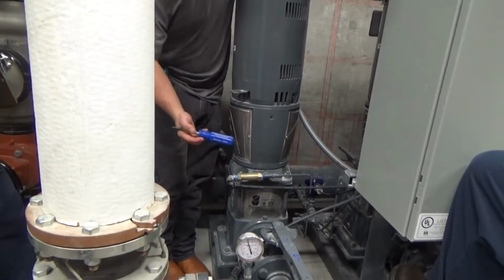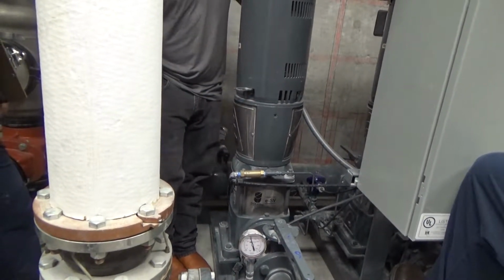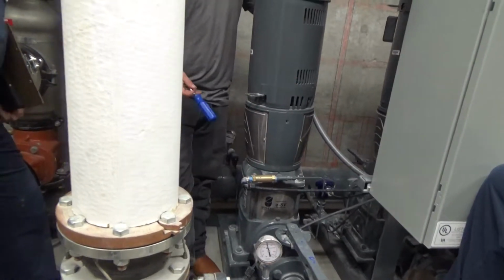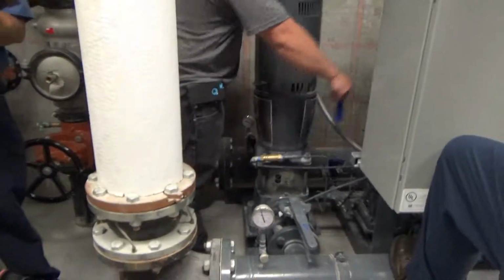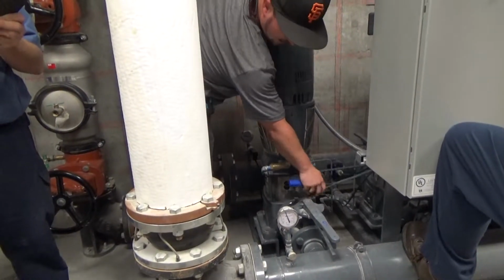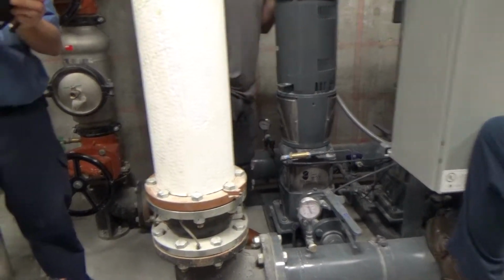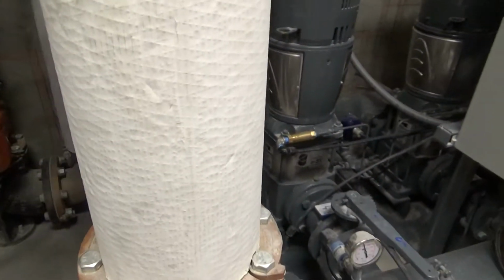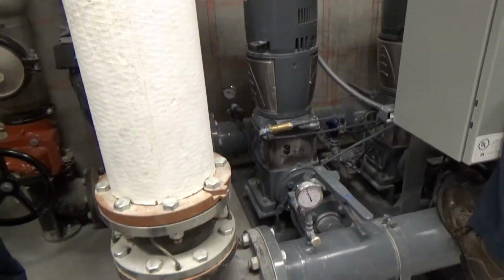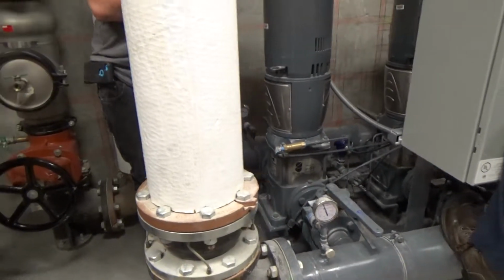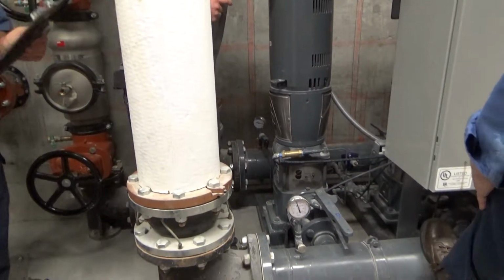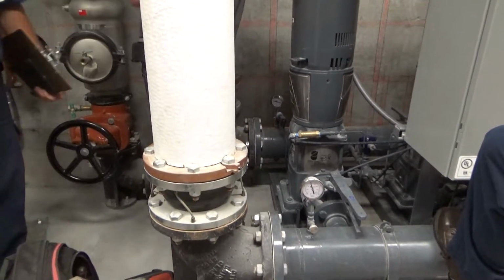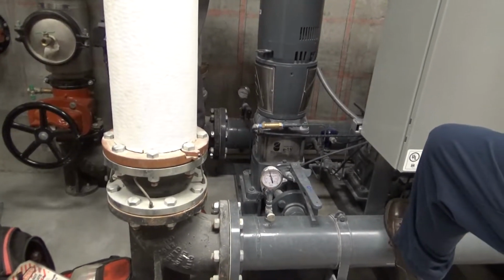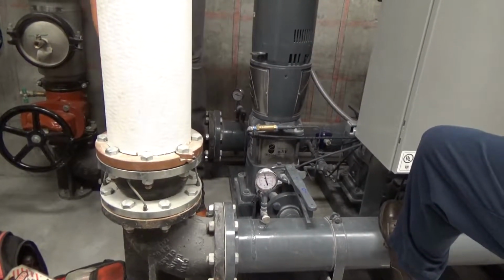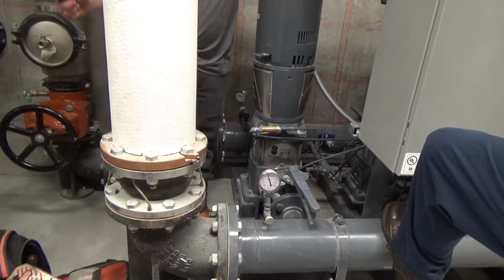Right here you have a temperature and pressure relief valve. Temperature 130, pressure 300. Each one is piped into this manifold right here and exits right here. So that's your extra protection on top of that temperature sensor. Those are another protection device to make sure that you don't put too much temperature on those seals, but it also does pressure. So if you ever hit 300 PSI, which these pumps are rated for, that's their max pressure, that thing will go off and go to a drain. Or, you know, there's a drain somewhere around here.